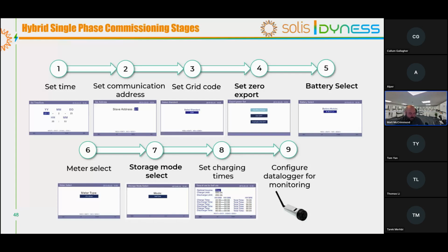You then have meter select. So we have a few different ways. Sometimes our inverters, if they've been made for markets like Germany or Austria, or they somehow managed to make it into the UK market, might have three-phase meters. We did historically have three-phase meters also. They are bigger in size, so sometimes they can be an issue for boards, etc. But you might find that the inverter comes with a three-phase meter. It is possible to use a three-phase meter using just a single phase or the L1 of that meter. But again, you can contact our service department and we can talk you through that. Or we can look at getting you a replacement meter if it's really required, but it does work as normal.